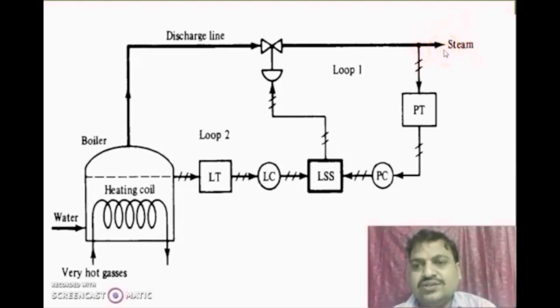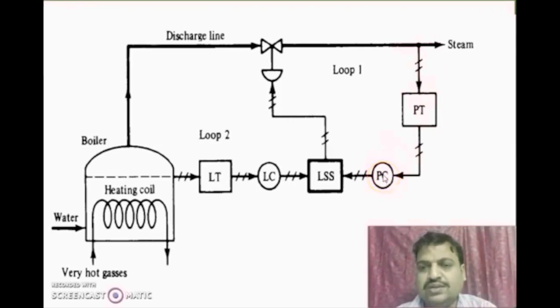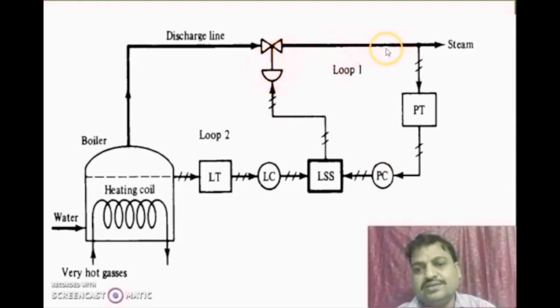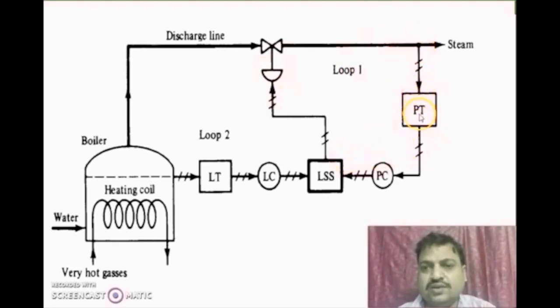Under normal or steady-state conditions, we are getting the required value. But if a disturbance occurs in the system, this value will deviate. We are continuously measuring the pressure, so if the value deviates from the required value of 10, it gives information to the pressure controller. The pressure controller will change the outlet flow rate — for example, if we want 10 but are getting 8, we decrease the outlet value so that pressure increases. In this way, by operating this valve, we can change the pressure or flow rate of the steam using an ordinary feedback loop.